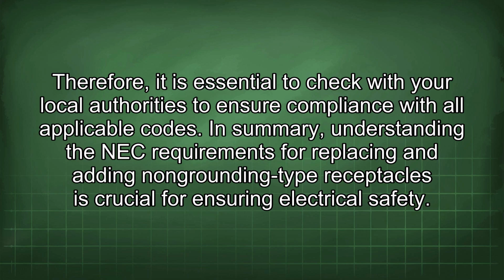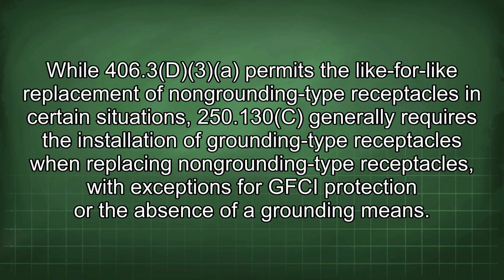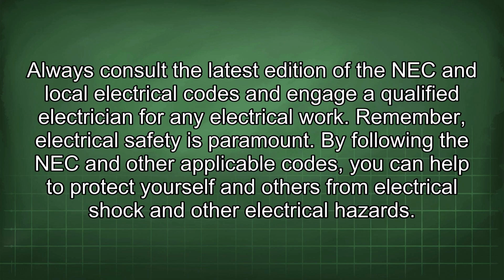In summary, understanding the NEC requirements for replacing and adding non-grounding type receptacles is crucial for ensuring electrical safety. While 406.3D3 permits the like-for-like replacement of non-grounding type receptacles in certain situations, 250.130C generally requires the installation of grounding type receptacles when replacing non-grounding type receptacles, with exceptions for GFCI protection or the absence of a grounding means. Always consult the latest edition of the NEC and local electrical codes and engage a qualified electrician for any electrical work. Remember, electrical safety is paramount. By following the NEC and other applicable codes, you can help to protect yourself and others from electrical shock and other electrical hazards.